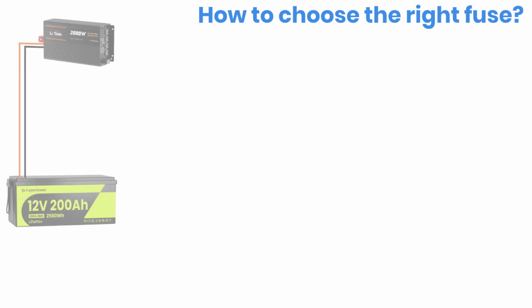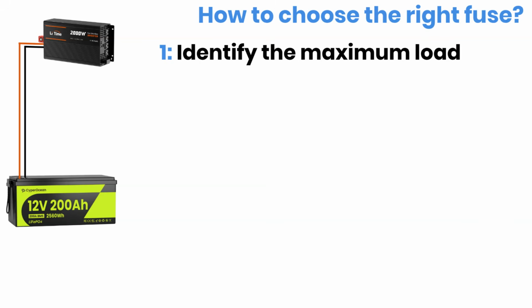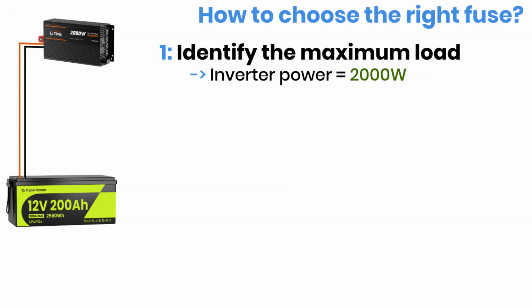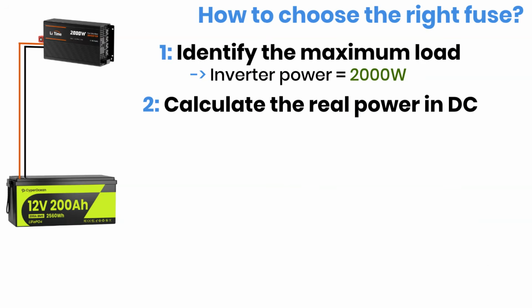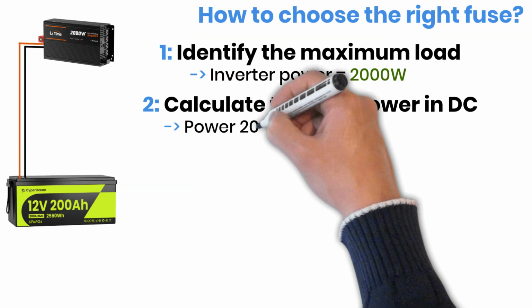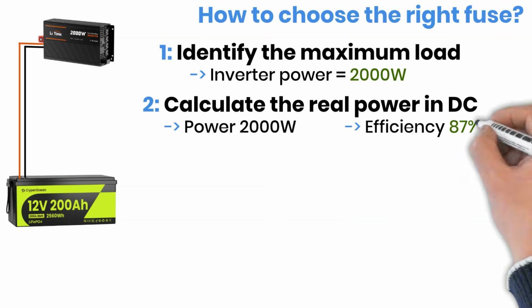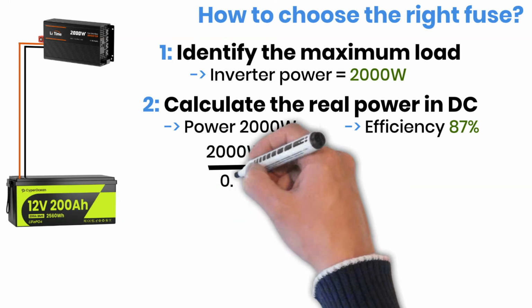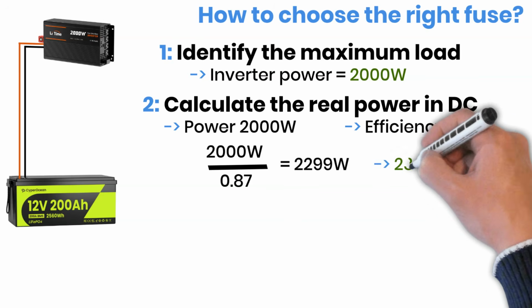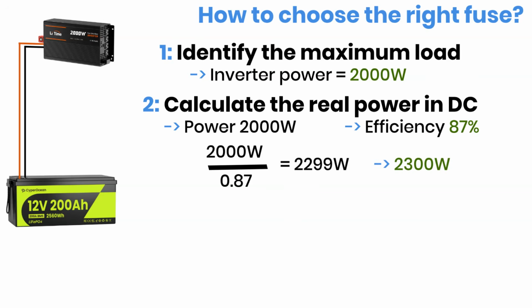First thing, we look at the inverter. In our case, it's rated at 2,000 watts. That means, at full load, it can supply a 2,000-watt device. But here's something important a lot of people forget. Your inverter is not 100% efficient. Some energy is always lost as heat when converting from direct current to alternating current. Let's say this inverter is about 87% efficient. So the battery actually has to supply more power than 2,000 watts. We calculate it like this: 2,000 watts divided by 0.87 equals around 2,300 watts. So now, instead of 2,000 watts, we use 2,300 watts as our real power demand.